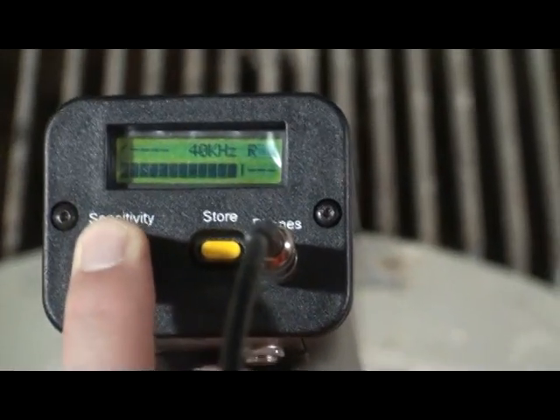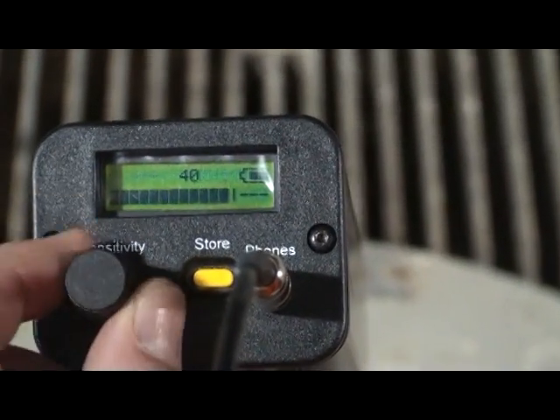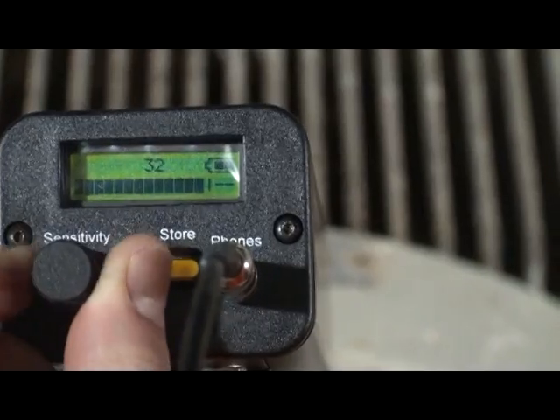Click the sensitivity dial to move to frequency and adjust the frequency to 40 kilohertz. Click the dial again to adjust your sensitivity. If the sound is too loud, bring it into range by spinning the sensitivity dial until the decibel is present and the sound is clear.